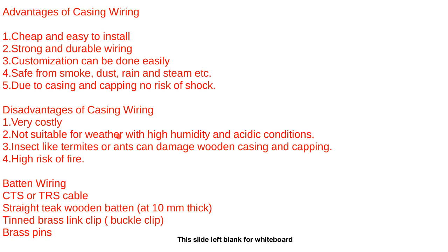So those are the disadvantages. The risk of fire, not suitable for outdoor, therefore they are mainly used in indoor wiring systems. They are subjected to harsh weather conditions because you just lay your cables there open. You cannot use this type of wiring system for voltages above 250 volts. And the last one, heavy wires are not recommended in this type of wiring system.